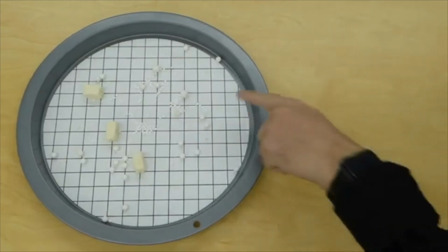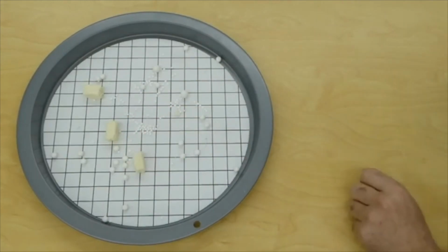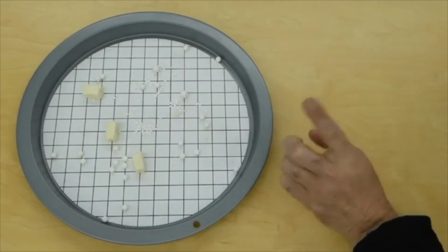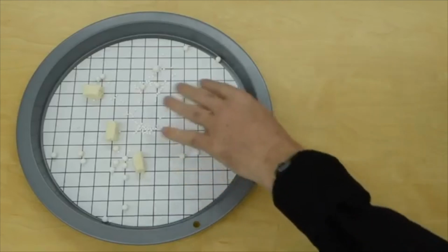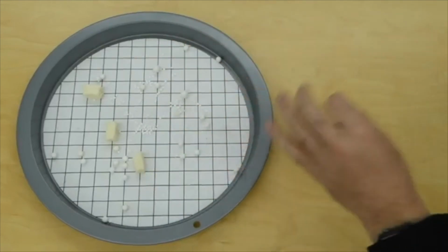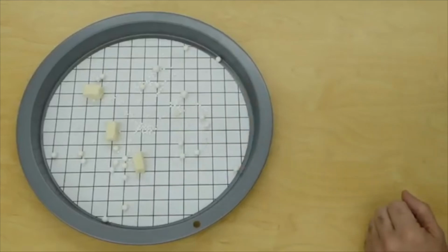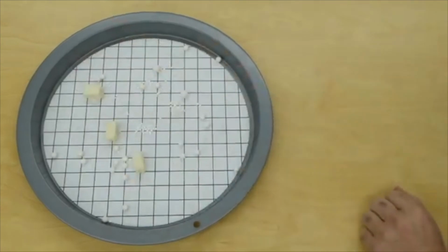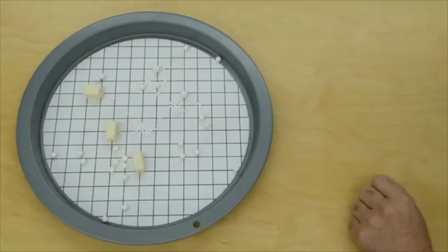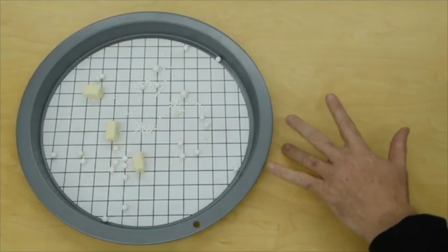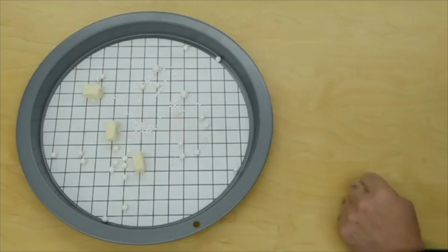One final point. In this case, I've used mints, and the reason for that is the size is the only thing that gets evaluated. The material doesn't. So it doesn't matter if these are particles of steel or bronze or rubber or wood or some organic material. It doesn't matter at all, because we are only evaluating size with these tests. So whether it's an NAS sample or an SAE-AS sample or an ISO sample, it's actually size is all that matters. So in this case, they're all white, and we can think of them as only size.